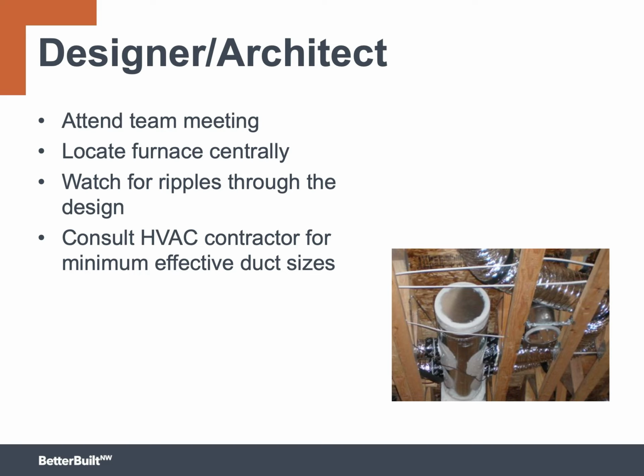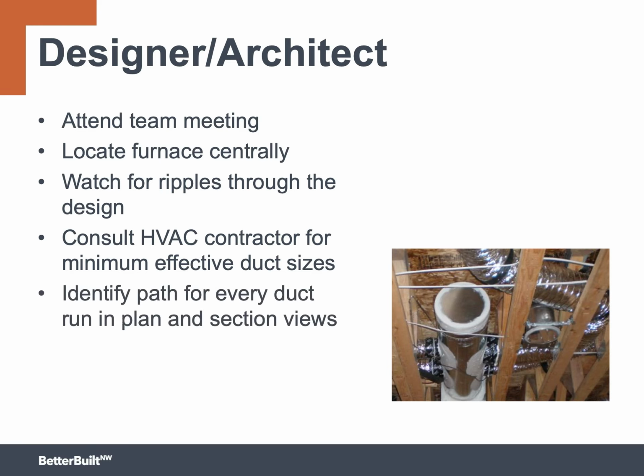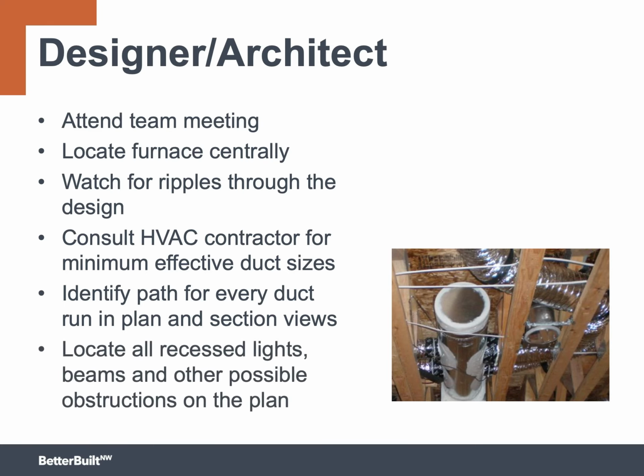The designer needs to take this to the level of literally locating every duct path from the furnace to the supply registers, and the designer also needs to represent that on the drawings in both plan and section view. And don't forget all those possible obstructions. For example, beams, ceiling light boxes, gas lines, and other potential places that might interfere with the duct runs.